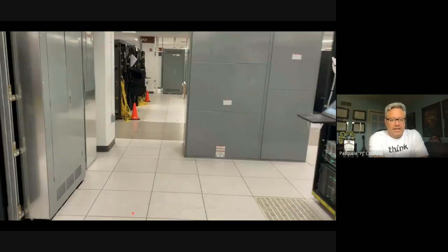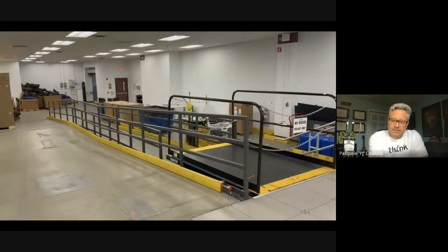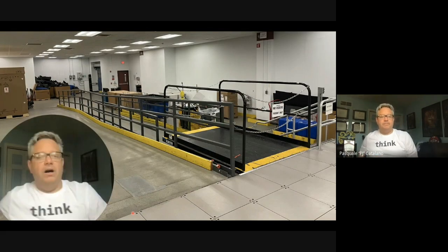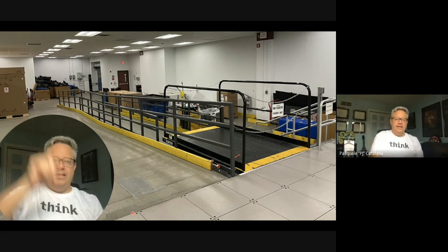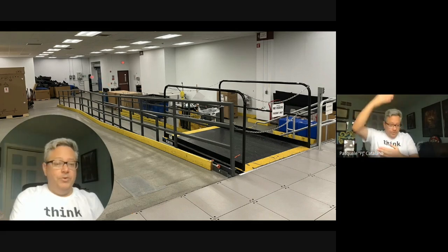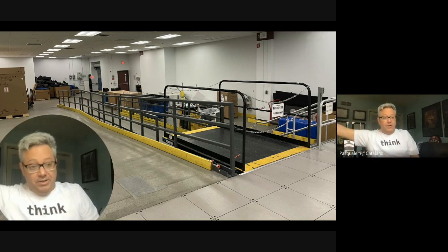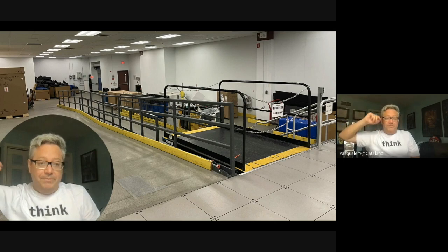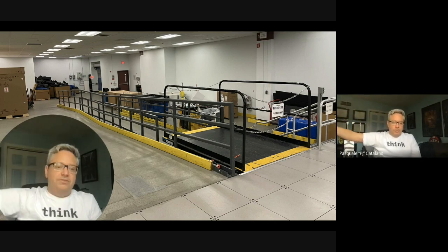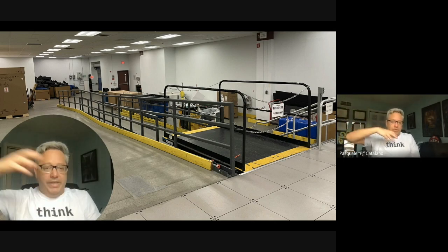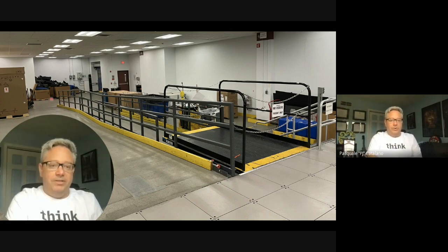We got a couple more stops coming, but one question I often get asked is, well, how do you get the mainframes onto the 30-inch raised floor? Well, here's your answer. What you're looking at in the back here is like a loading dock door that would open and close. Just beyond that is actually a real loading dock where trucks would come and drop the mainframes off for us. So manufacturing builds them or ships us the parts. We then push the system up onto the floor. There's a ramp here for a smaller system. There's a lift here that gets the systems.